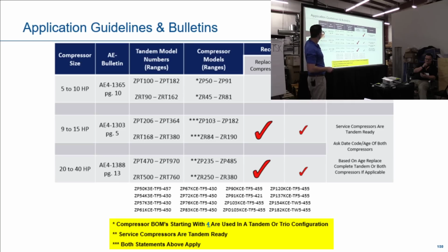Like 5 to 10 horsepower. This AE bulletin, ZPT 100 to 182, says replace the tandem. No tandem service replacement. And we might have updated this too. This is a little bit older slide. But then we get down to 20 to 40 horse. Look, you can replace the single compressor based on age.